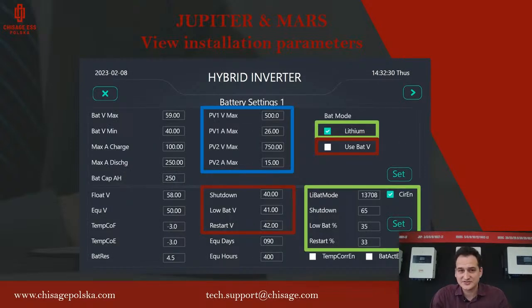On the first page of battery settings, we have something like this. We have 2 battery modes we can use: lithium and battery voltage mode. If we pick lithium, all the information we have to fill in is in percentage. In the green box at the bottom, we put the shutdown percentage, low battery percentage, and the restart percentage. If we use battery voltage mode, we fill in this red frame: shutdown voltage, low battery voltage, and restart voltage.